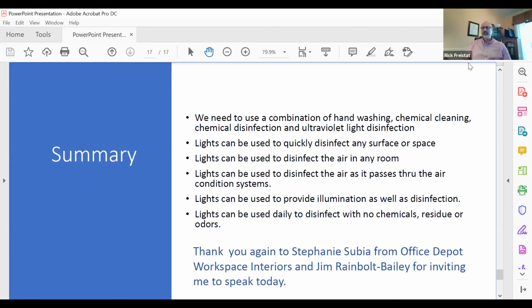The problem that comes in, if I can jump on that for a second, is that the best case scenario would be fresh air comes into the building, runs through a room, and goes straight back out, so we get fresh air again. The problem is that if you're not matching the outside temperature and had to cool the air all the time instead of recirculating already-cooled air, your existing equipment likely wouldn't be able to handle it and function well. So in a perfect world, sure, we'd bring in outside air, let it do whatever it does inside the building, then vent it back out and bring fresh air in again. But you're bringing hot air in, cooling it, running it through the building, venting it out, and bringing more hot air in constantly. There's usually a damper and some percentage split of fresh air versus recirculated air in a building. So that's some of what they're looking at too: how much fresh air can I bring into my building with my existing equipment, because that makes a big difference as well.